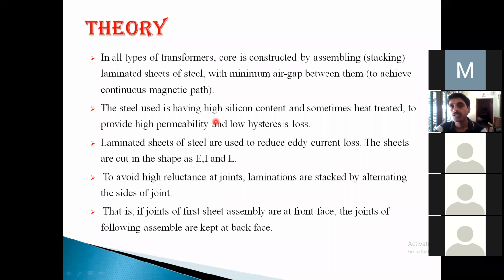In all types of transformers, the core is constructed by assembling laminated sheets of steel with minimum air gap between the laminations. Steel is used having high silicon content, heat treated to provide high permeability. Permeability is very important, maximum permeability. That's why the flux losses are very less. The flux is constant. Laminated sheets of steel reduce the eddy current loss, and to avoid high reluctance at joints, laminations are stacked. So the sheets are connected as laminations.